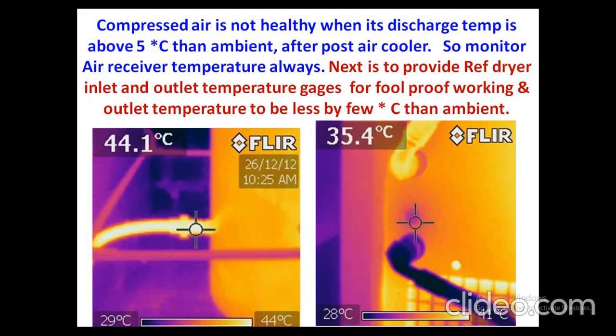For a 1000 CFM, 160 kilowatt compressor for a textile mill, they go for almost 1500 or 2000 CFM dryer capacity. The dryer capacity minimum has to be 50% more than the compressor capacity. Refrigeration dryer, I mean to say. Automatically the temperature has to come down. You don't allow the dryer to derate because of higher input temperature to the dryer. The post air cooler has to definitely work correctly, and the water has to be removed at the water separator, at the air receiver, and at the refrigeration air dryer. The temperature monitoring, especially in the compressor house, will definitely give a lot of energy savings in compressed air generation.